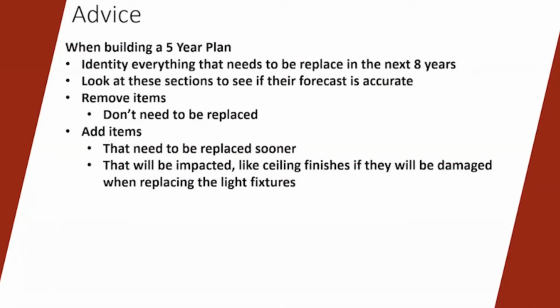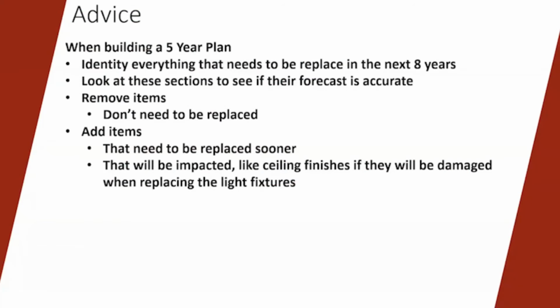But as far as advice from this, the first advice was kind of obvious without really proving that it's obvious: go to whichever rating is closest in age. But the advice that I give all my clients is when you're putting a 5-year plan together, you need to go out and look at your scenario for the 8 or 9 years. And that's the list where you start. Then we want them to go lay eyes on those things to say, is the Builder forecast accurate? Do I really believe that this is going to be in this time frame? And that's why we go out 8 years, because we know there could be error that was optimistic in its rating, so it's put out further than it should be. And there are things that are pessimistic that show up in that list that really aren't going to expire that soon, and they need to be pushed out. And then the other reason we like to tell our clients to go out and look at these things is what no software I've seen does yet.